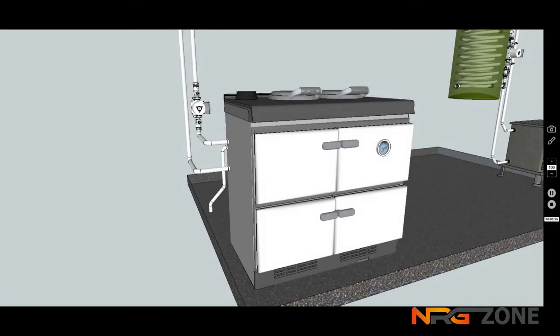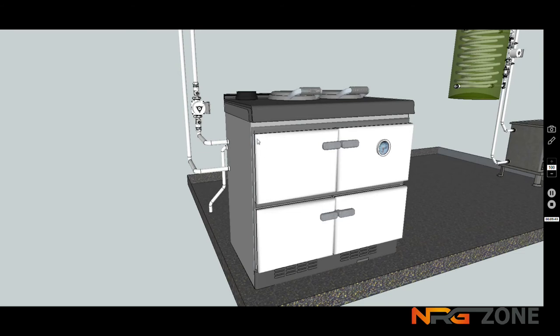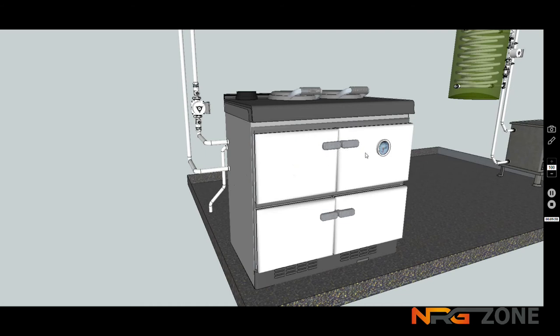What we have is the pump on the return connection, which in this situation, as I said, is at a higher point than the flow, goes through. The combustion process creates condensation, and that condensation should be conducted in plastic pipe away from the cooker. It's very important to follow manufacturer's instructions, especially with any unit as powerful as this cooker, or any oil burning or gas burning situation. And particularly when condensation is involved, it's so easy to do it right, and it can cause so much hassle when it's done wrong. The instructions are so important to follow.